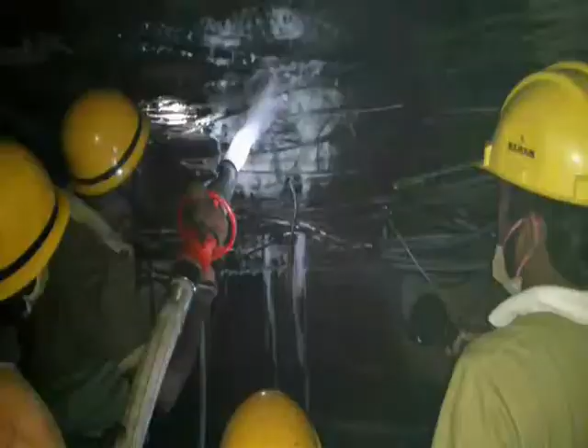Irrespective of cadre, all the engineers and technicians grouped together with fire personnel to enter and put out the fire. They broke open the other door and started to control the fire. Fire personnel tried carbon dioxide foam to put off the fire. The fire was so intense that it took more than 1 hour to put out. As a result of the fire on the cable insulations, all the cables were joined together, making it difficult to identify individual cables. At this time nobody was aware that part of the nervous system of the power plant automation was burning beneath the unit control room.